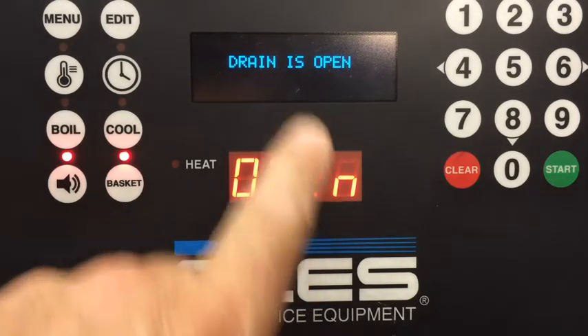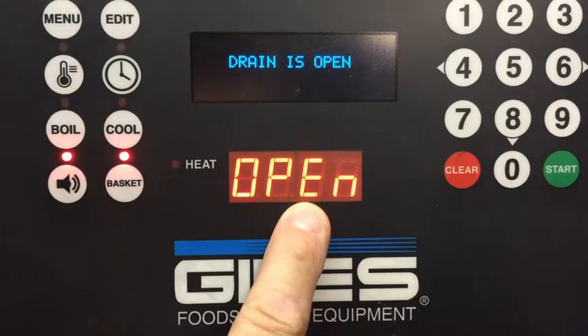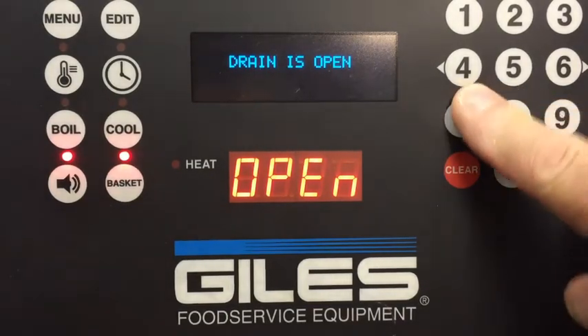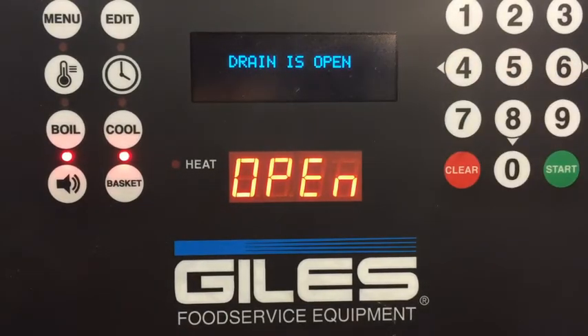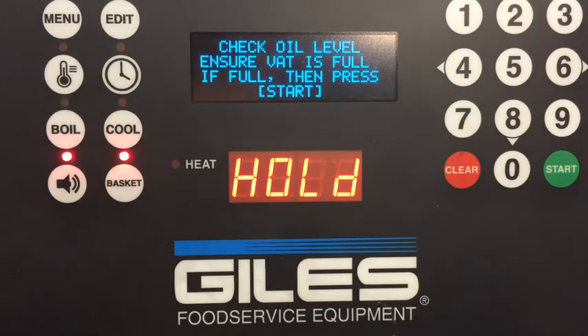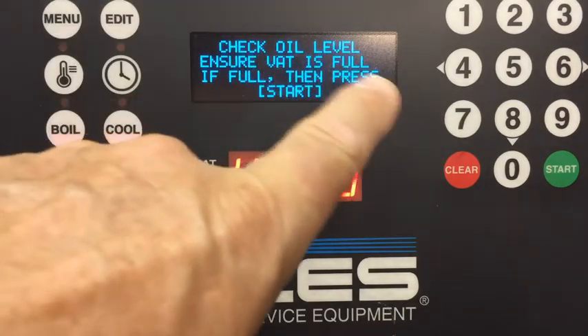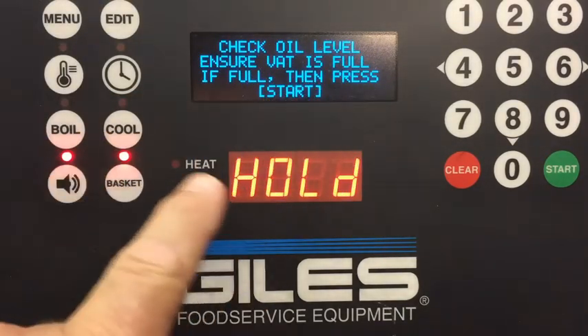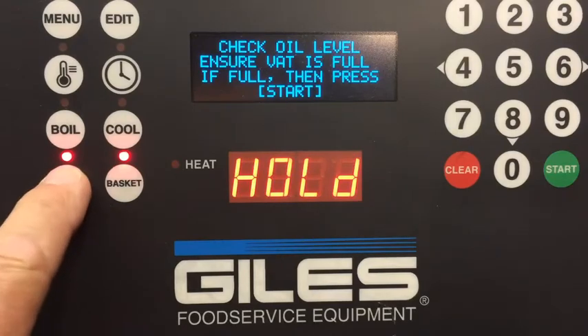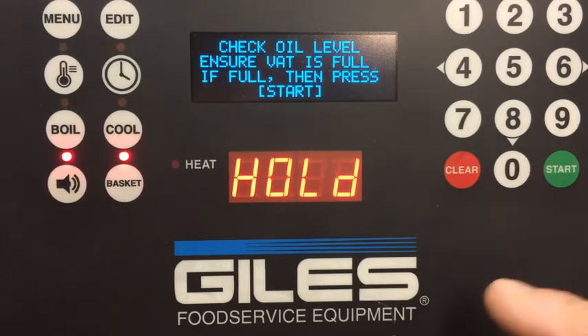It says right here the drain's open, and it tells you open right here. You can press whatever button you want. Nothing's going to happen until you clear that drain open message. So once we clear the drain open message, now it's going to go ahead and give us a check oil level, ensure vat's full, and then press start. You can silence it. You're ready to go.